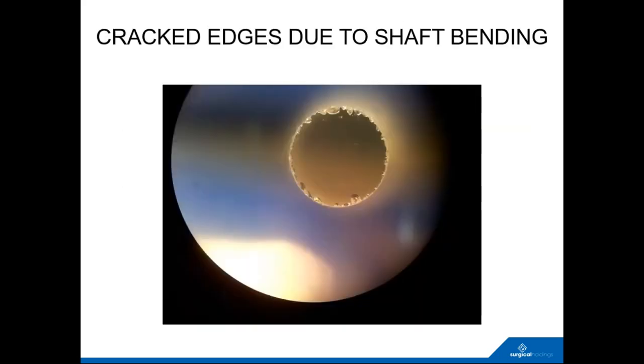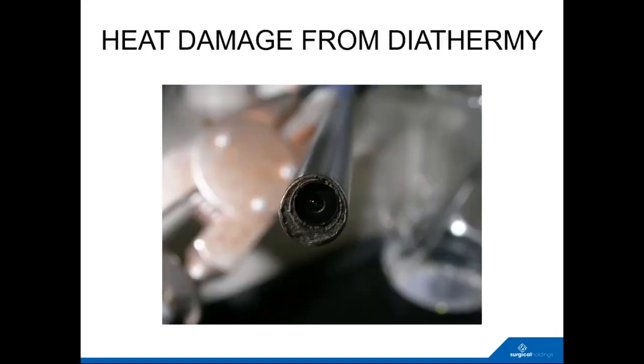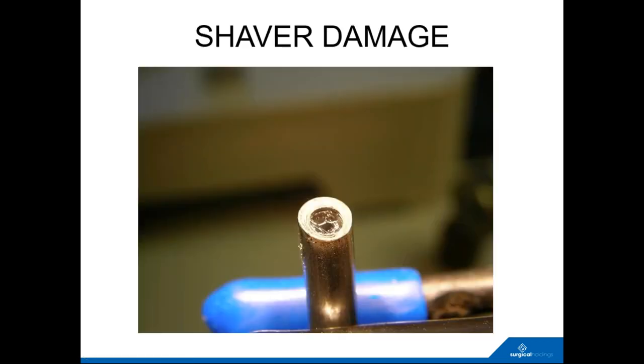Giving you a few examples of pictures of damage to scopes. This is due to shaft bending, classic cracked edges around the circumference of the instrument. Heat damage, you can see particularly here, there's quite significant heat damage that's occurred at the tip of that. That's the distal window of the instrument.